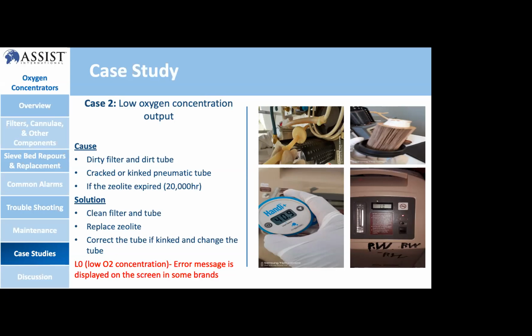As a solution, we work on the filters. That means we have an intake filter, a compressor intake filter, a gross filter, and also a HEPA filter. We clean those, and normally that fixes the problem for the machines. The other related problem is the replacement of zeolites, because zeolites expire. In other cases, the zeolite is just full of moisture. The moisture enters the zeolites and blocks them, or it lowers the pressure delivered to the patients.